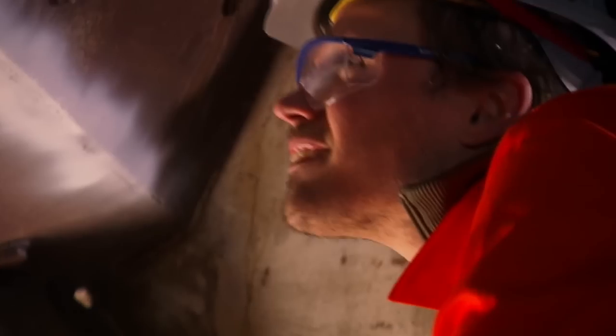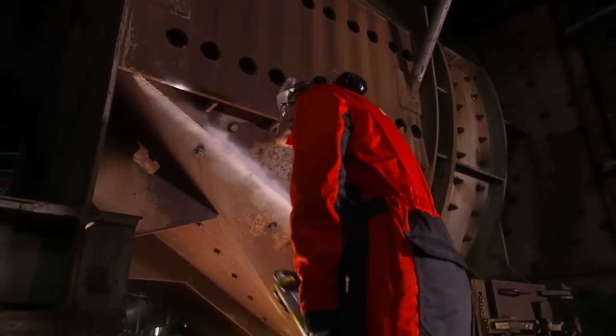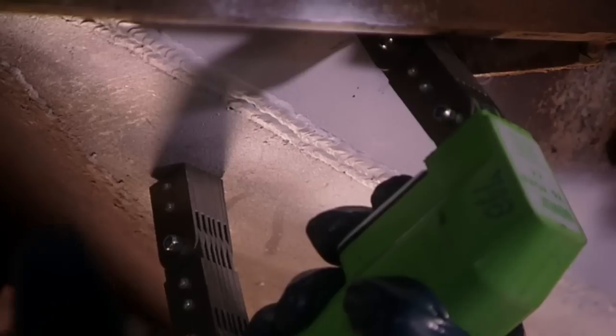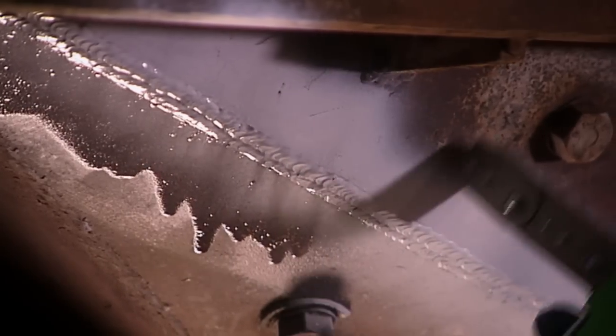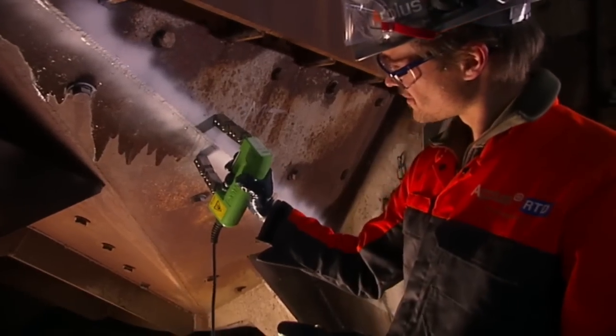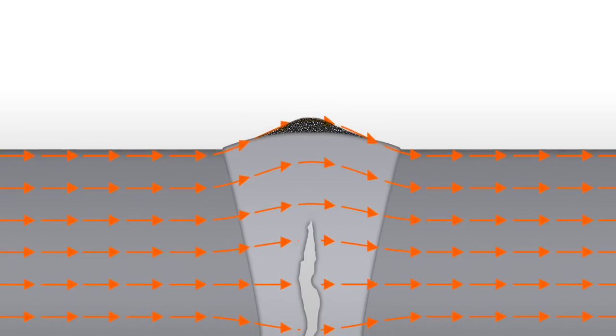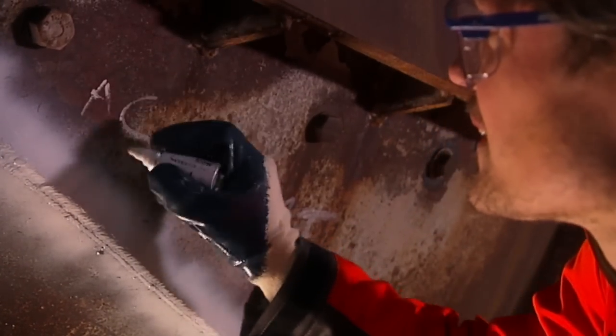To make sure the buildup of the iron particles is clearly visible, in some cases the surface is first sprayed with a thin layer of contrast paint. The examiner carefully checks that he didn't miss anything. He then applies a magnetic field crosswise over the surface, then sprays a black suspension powder — a liquid in which small iron particles are suspended that react to the magnetic field. The examiner watches the iron particles' reaction carefully. Then the MT examination is done in the 90-degree direction to ensure 100% coverage. In this case, the weld did not indicate a leak field. The examiner indicates that the result is acceptable.